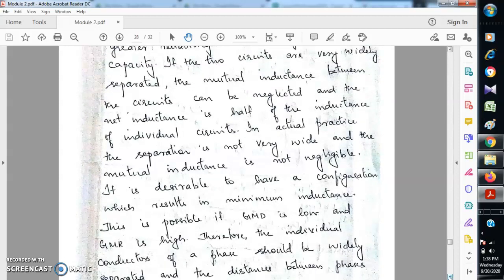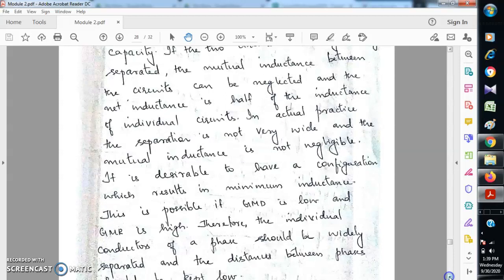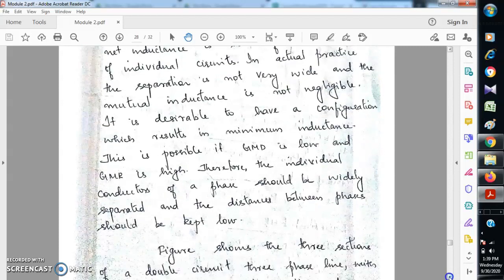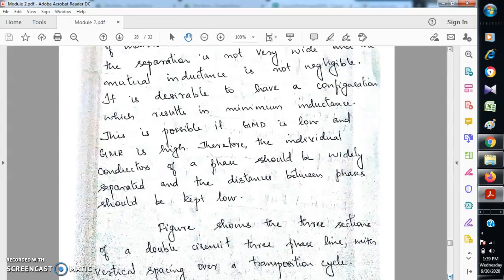For minimum inductance, the geometric mean distance should be low and the geometric mean radius should be high — that is, r' should be high and the numerator of the log should be low. Therefore, the individual conductors of a phase should be widely separated, and the distance between the phases should be kept low. The distance between phases, that is the numerator part d, should be kept minimum and r' should be maximum.